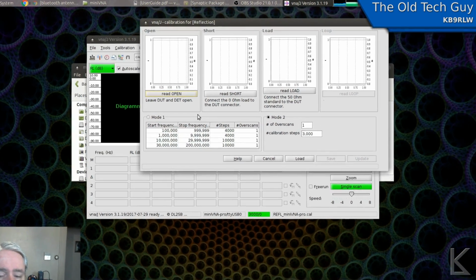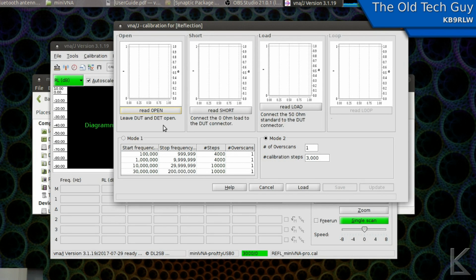Calibration. Did I cover calibration? I might have had my face in the way. The calibration window, you plug in those little calibration blocks and you can read open, short, and load to make the measurements. And then once you've made your calibration measurements, you'd hit the save button down here to save the calibration for your device.